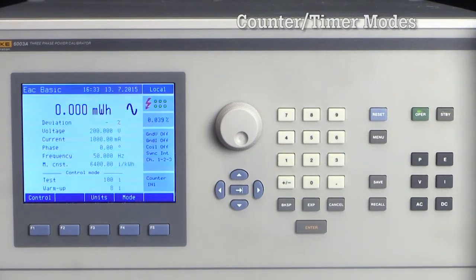The 6003A starts to count energy pulses. After it has received the amount of warm-up pulses prescribed, the test will run for the amount of pulses set in the test. Counting is finished after the set number of predetermined test pulses is reached. The display now shows energy delivered during the set number of test pulses and displays the deviation from nominal as a percentage.